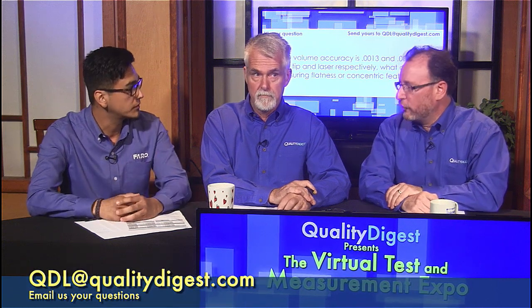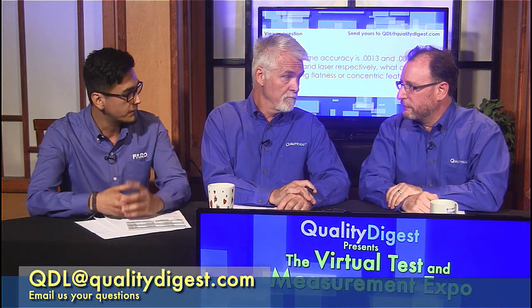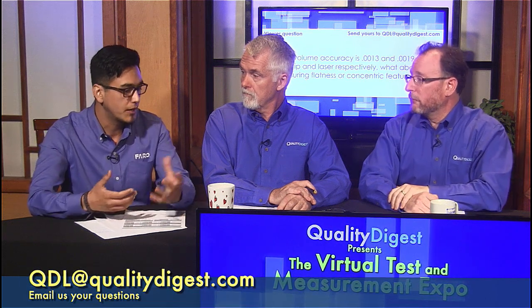So the previous arm was a FARO Edge, and that came out 7 years ago. You know how technology progresses so much nowadays. There's been a 25% reduction in the weight, so it's a lot more ergonomic. It feels like an extension of your arm, whereas the previous arm could get a little fatiguing. Not to say it was hard to handle, but that's just one of the advancements, as well as a bump in accuracy and data capture for the laser scanner. We're able to capture laser data 5 times as fast as before. There are also shock absorbers in the arm for setup. That lightness really helps with the portability, which FARO is all about. We're not trying to replace your CMM. We want to work with your CMM, with your current inspection process.